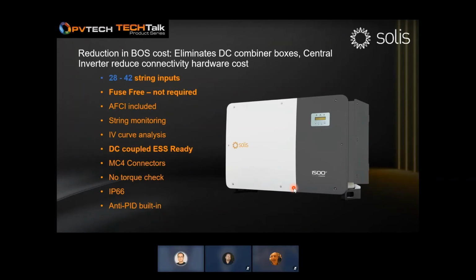If you have questions about anti-PID on our 255 and how it is used, I usually get that question quite a bit, so let me just explain a little. On our inverter, we have built in the anti-PID device to raise the ground voltage of the DC side. So we make sure your module will never experience a negative voltage, so the current, or the electrons, will never flow backward towards the module. And that actually helps reduce the degradation that could happen to your module.